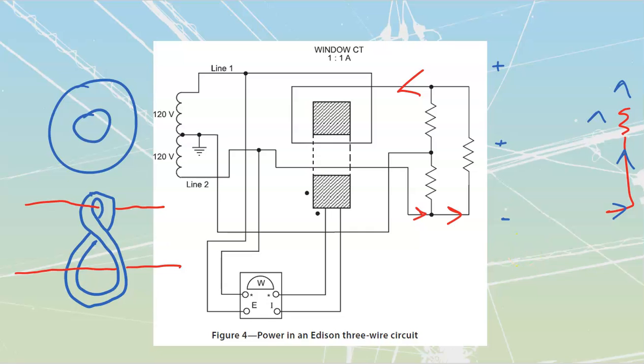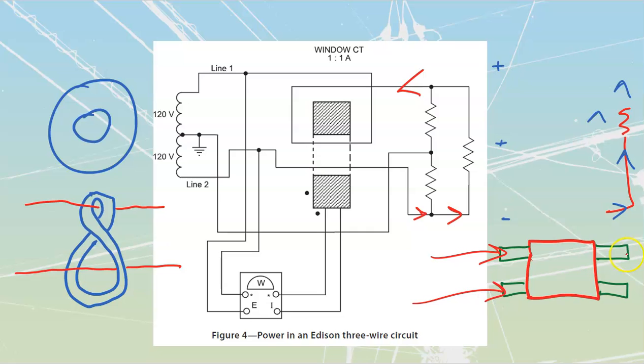And what that gives us is a CT, our standard single phase CT, that looks like this, where it's going to be a big, heavy component we place inside of a cabinet, and it's going to have a bar here, a bar here, and a bar here. We will bolt our incoming lines onto one side, and we take our outgoing lines out the other side, to wherever our loads are, sub-distribution, etc. But all that they've done is take this thing and twist it around, because it would be way harder for them to twist the actual bar around, and it would be super confusing for us as electricians. I'm not going to lie, it would be. We would screw it up if we had to feed one line in from here and then back out to the other side. You're asking for problems at that point.